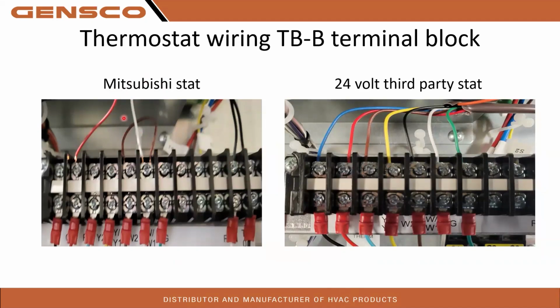If you guys want to change that non-adjustable stat as well, if you don't like 65, if you want to put it to 70 degrees, and you want to get a different new construction bullet style stat, you're welcome to do so. It doesn't matter. But that non-adjustable stat is going to land between R and W. And if you have a two-stage furnace, you're just going to put that jumper wire between W1 and W2. That way, if the stat does call, it'll kick on the second stage heat.